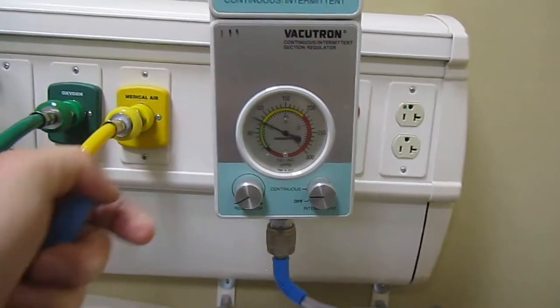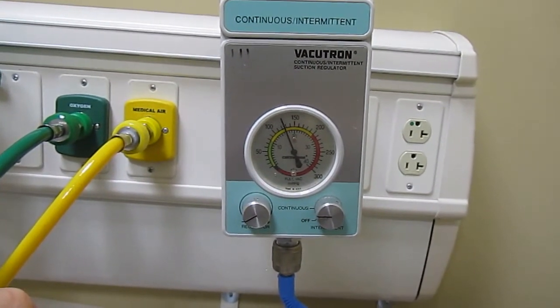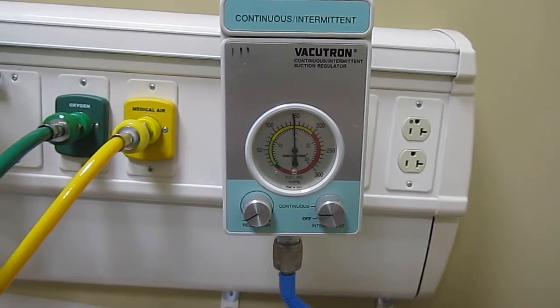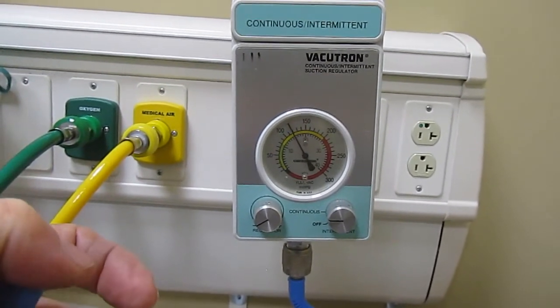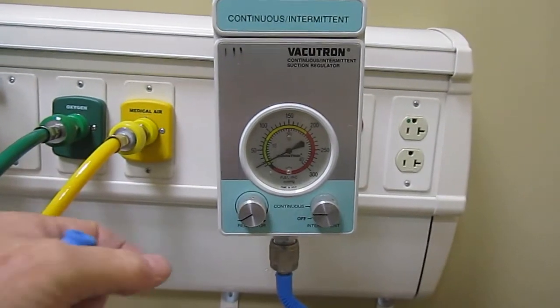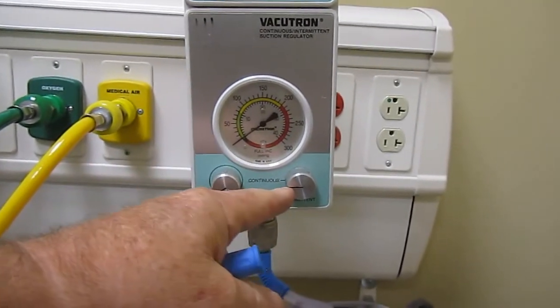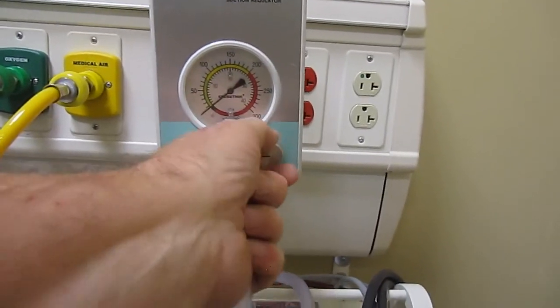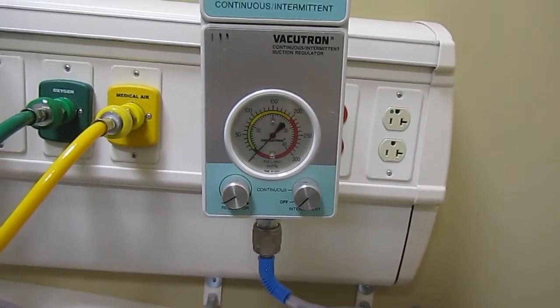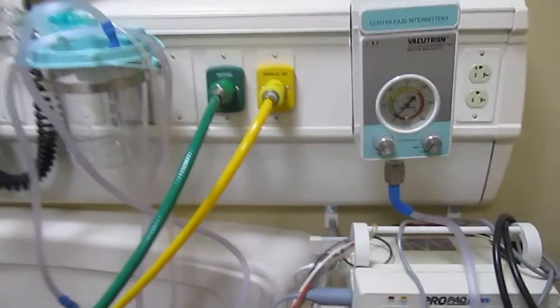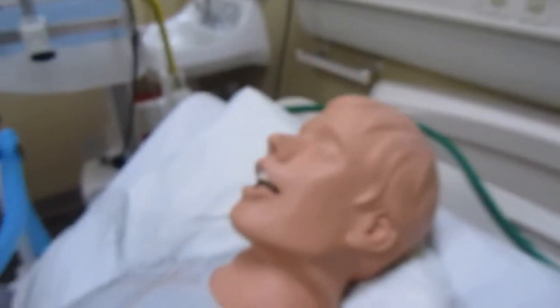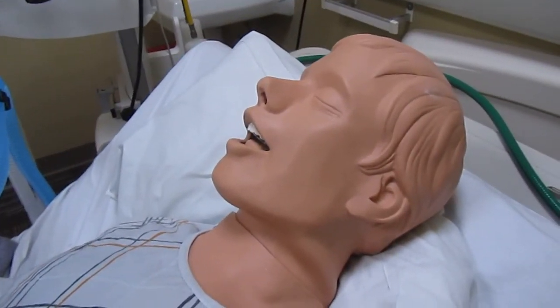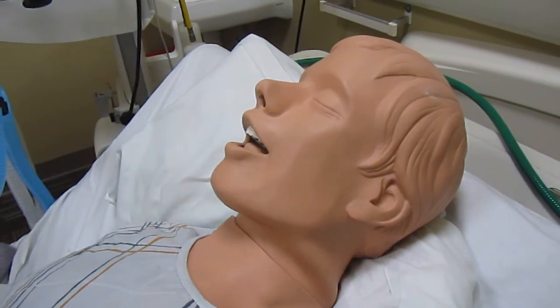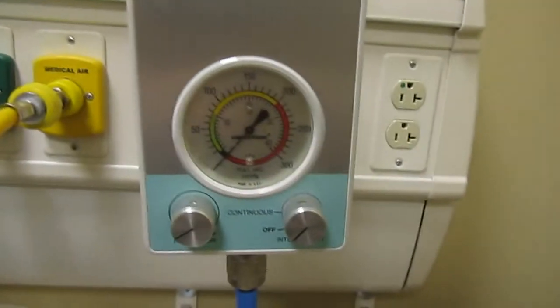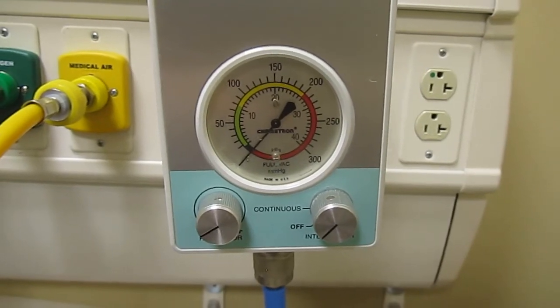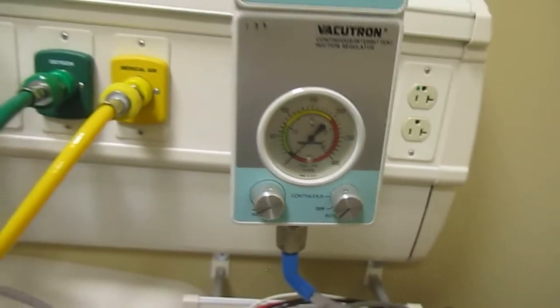I need more. Turn it up, turn it up, 150. That's how you check your suction. Let's turn this off now using the on and off knob. Very good. So the question is, how much suction do you use for an adult? The suction pressure is 100 to 120, and it is in millimeters of mercury.